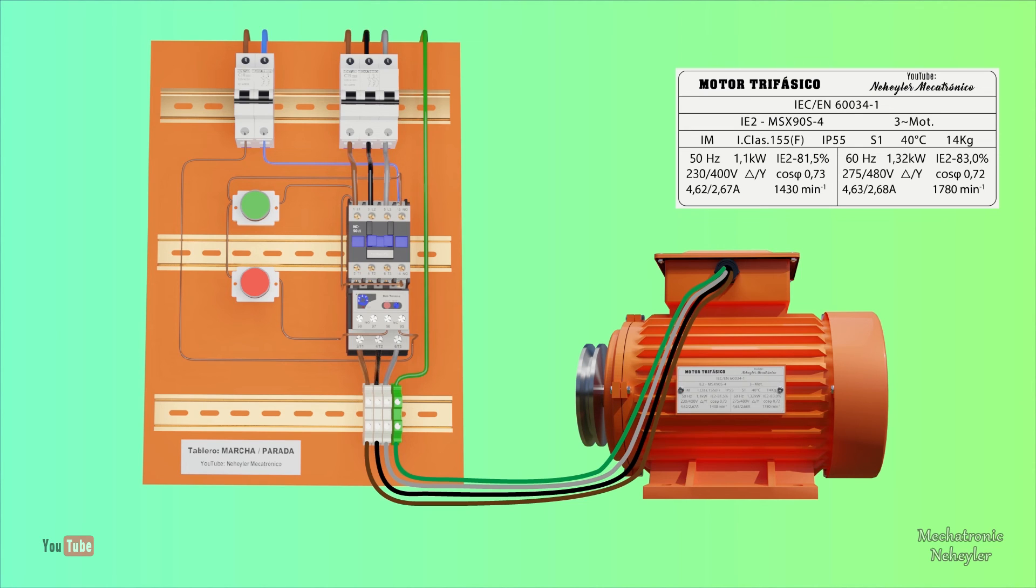Assuming we have a 400-volt supply at 50 hertz, on the nameplate it tells us that at that voltage value, the motor must be connected in star, and that the nominal line current is approximately 2.67 amps.